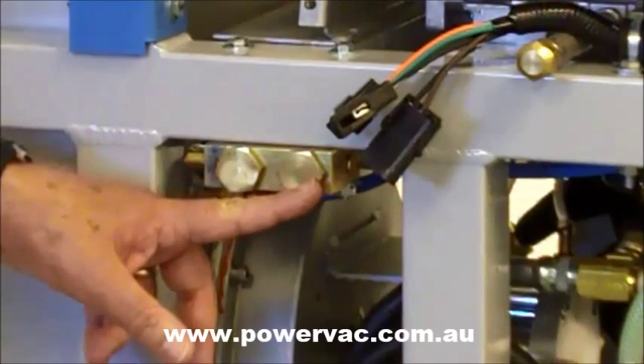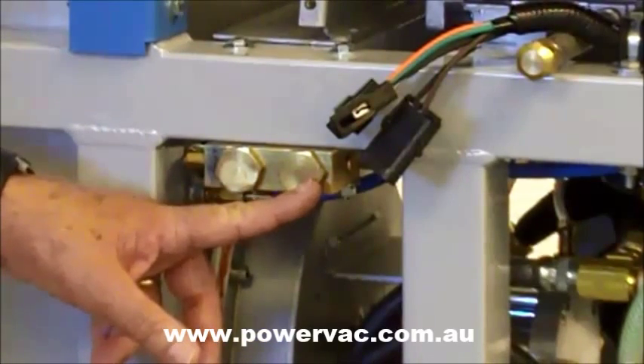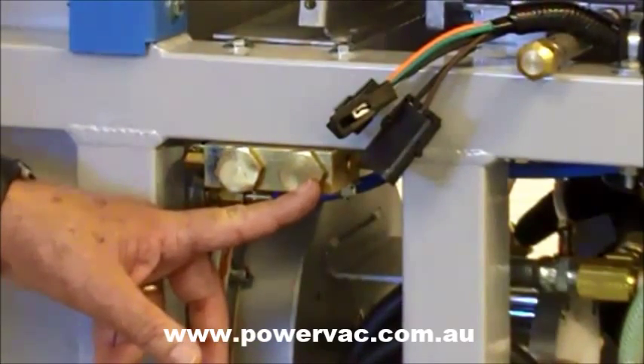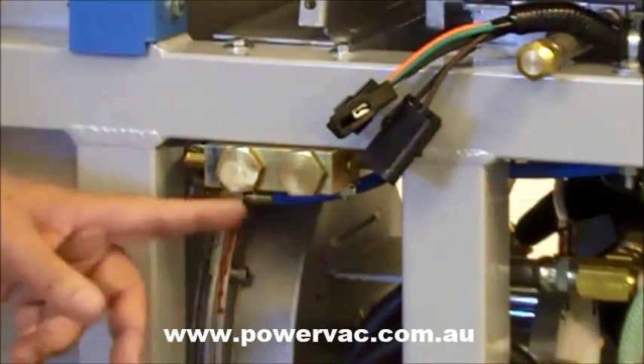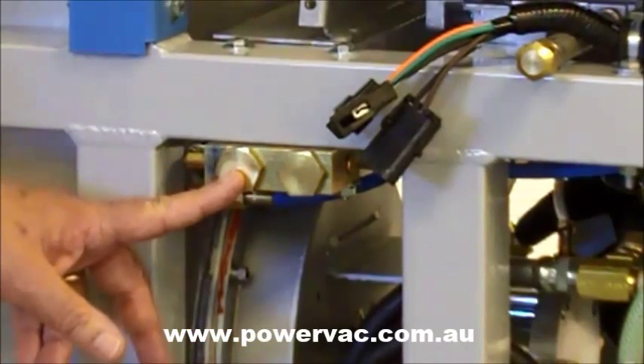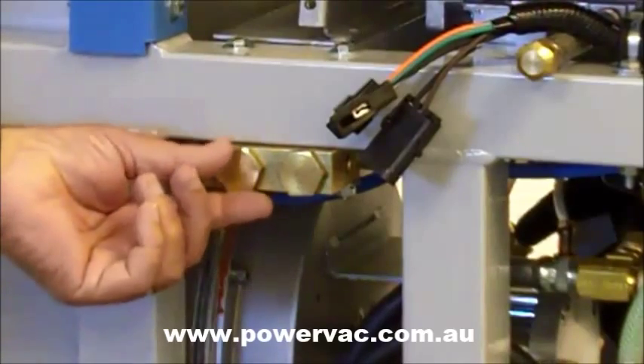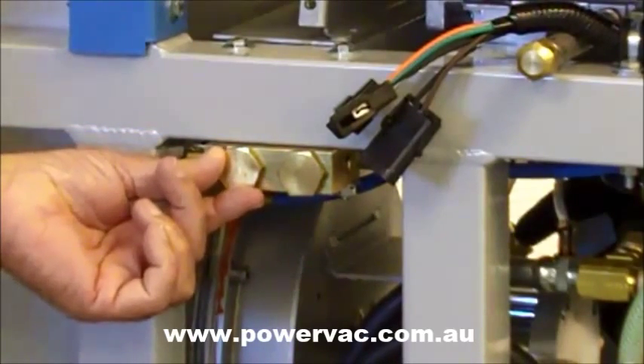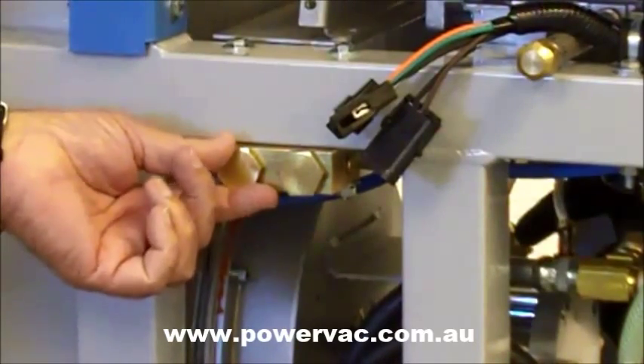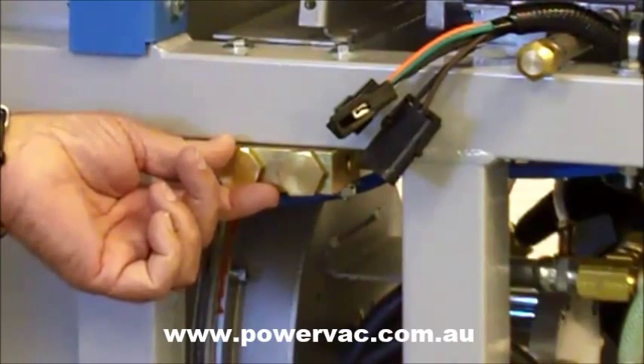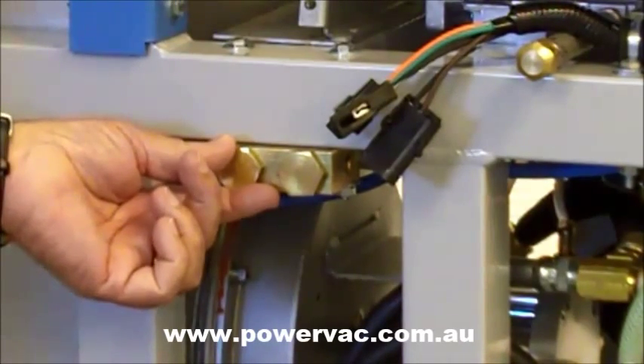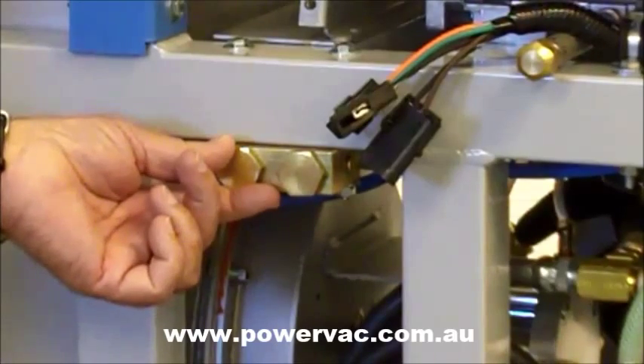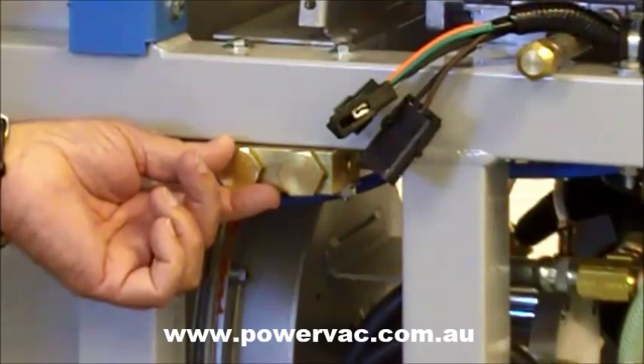The forward one is a filter. Again, it needs to be checked probably at least once a week, again depending on your location. The back one is the actual orifice itself. Once you remove the nut on the outside, the orifice is a stainless steel set screw with a hole drilled in it, and it just needs to be kept clear. It can be removed with a 3/16 Allen wrench.